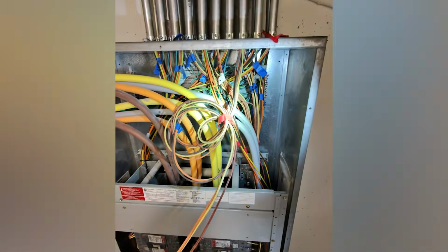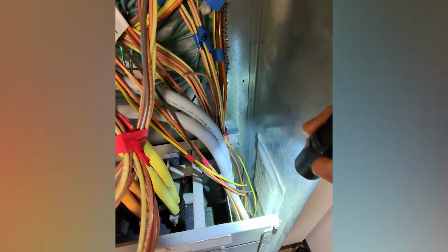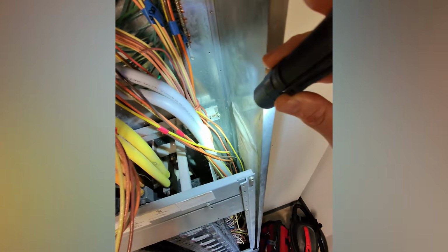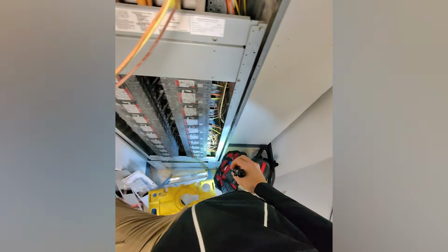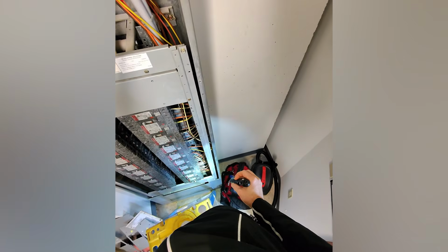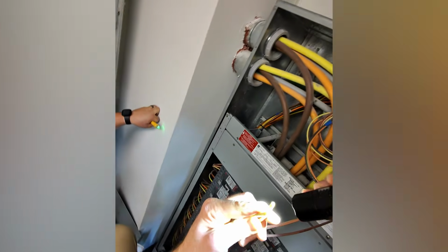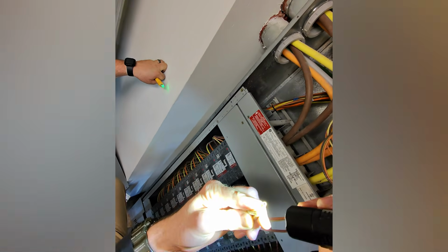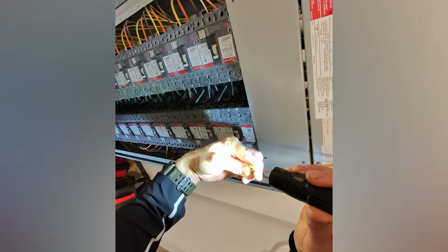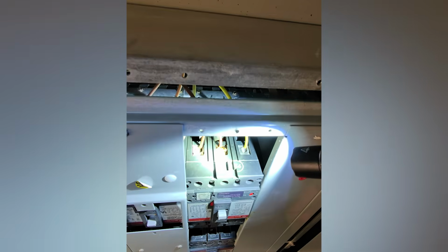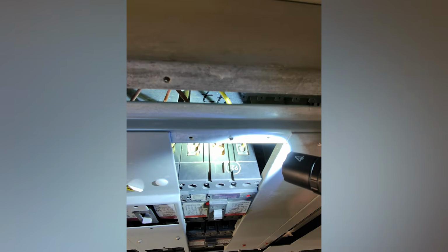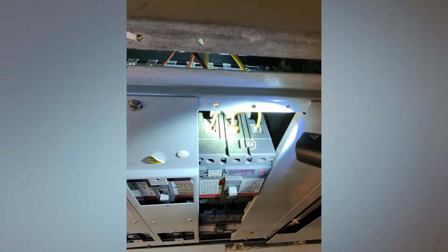It's the yellow wire. But that's dripping down our wire and running right into the breaker on that phase, just enough to get it nice and hot and then ground out at the terminal. Question is now, where's the water coming from? That was the grease you guys put in there? We didn't. It already came.